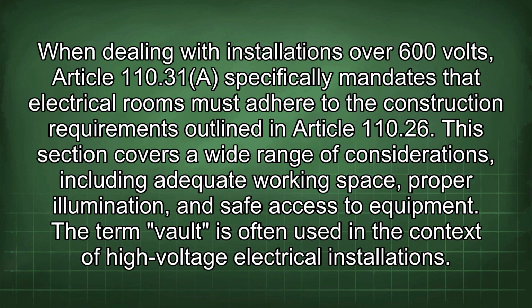When dealing with installations over 600 volts, Article 110.31 specifically mandates that electrical rooms must adhere to the construction requirements outlined in Article 110.26. This section covers a wide range of considerations, including adequate working space, proper illumination, and safe access to equipment.